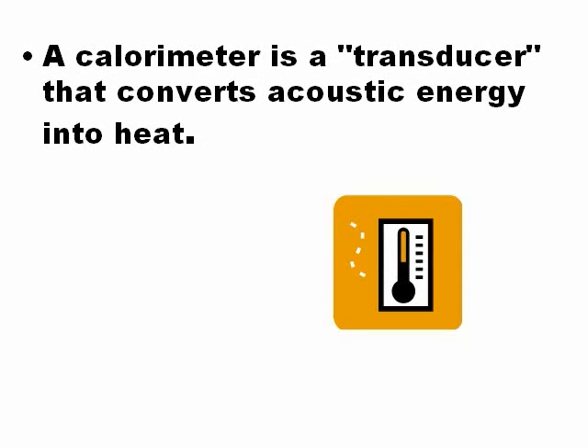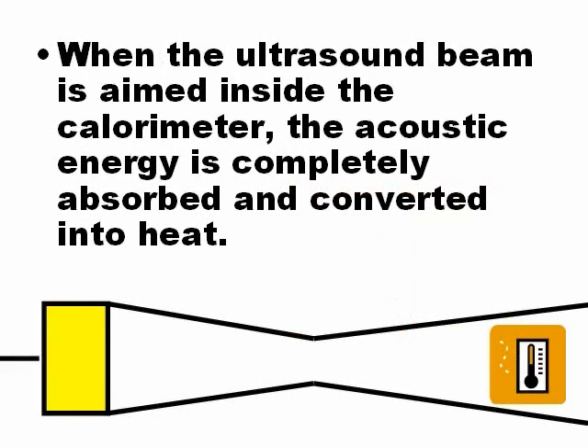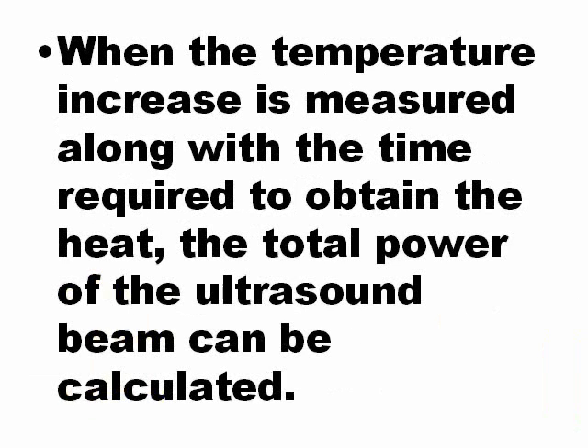A calorimeter is a transducer that converts acoustic energy into heat. When the ultrasound beam is in the calorimeter, the energy is absorbed, and that lets us measure the quantity of heat produced by the ultrasound beam. When the temperature increase is measured, the total power of the ultrasound beam can be calculated. This is to be sure the ultrasound beam is safe.